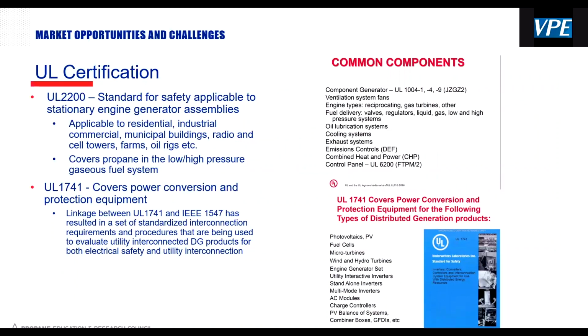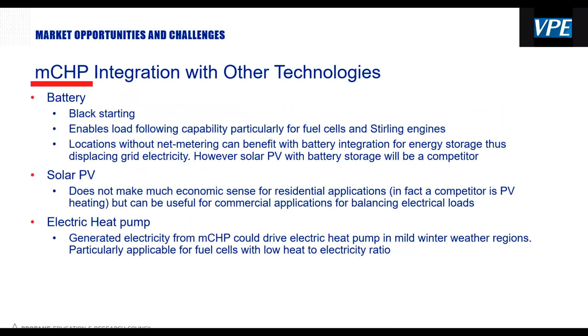On top of that, you need the UL 2200 safety certification for stationary engine generators. You also need UL 1741 certification, or IEEE 1547, for interconnection requirements. These are particularly important if you're grid tied, and especially if you're going to put power back into the grid, UL 1741 or IEEE 1547 certification is extremely important. All these different certification requirements also add to the soft cost when you're considering selling these units.